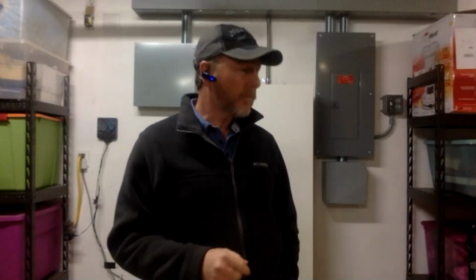Essential load, backup, whatever you want to call them, has a much different connotation than when you call this thing a critical load panel. The code has some very specific litany for that, like it's for emergency egress lighting, life support systems, things like that. Most battery systems are not fast enough to qualify to feed a critical load, so just keep that in mind.